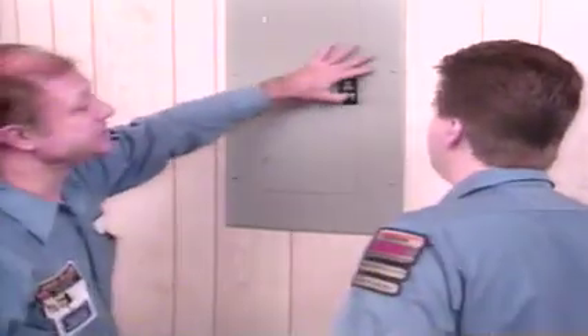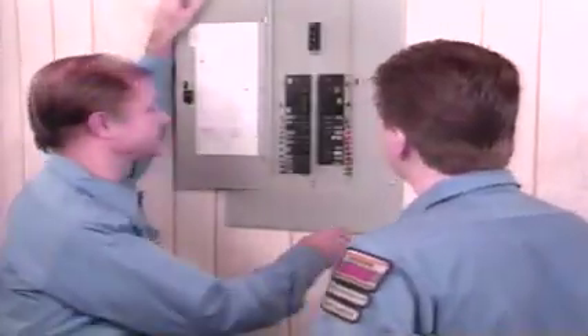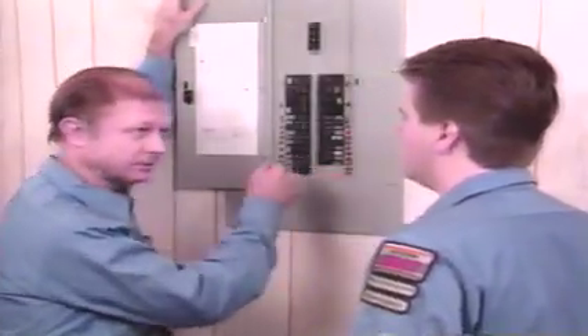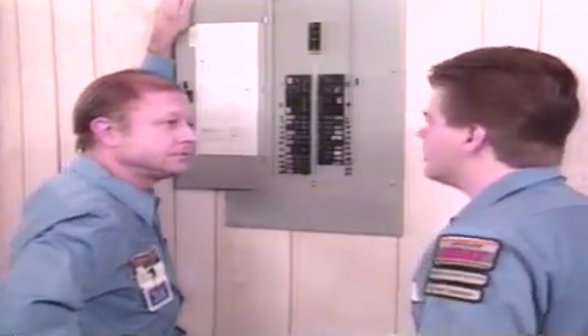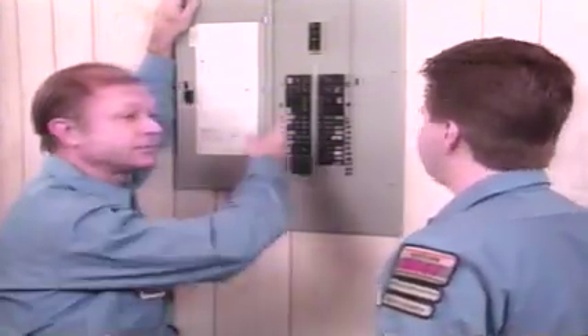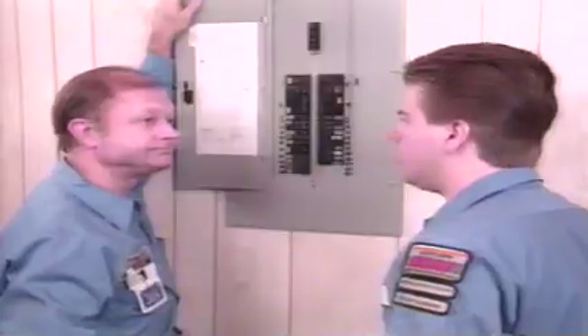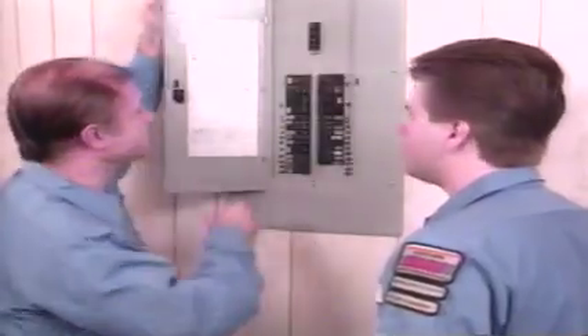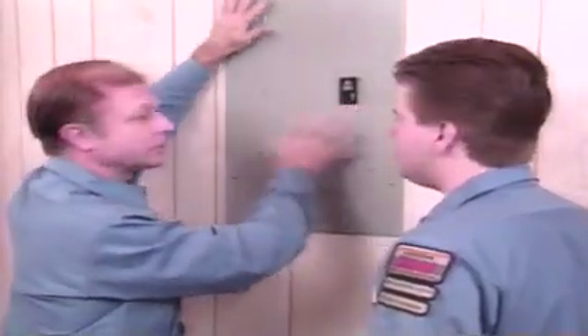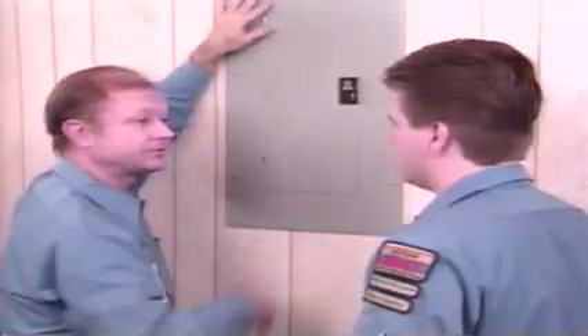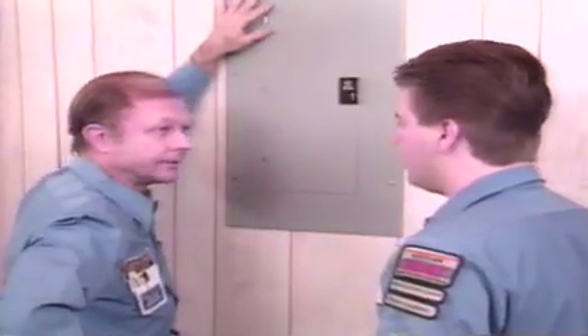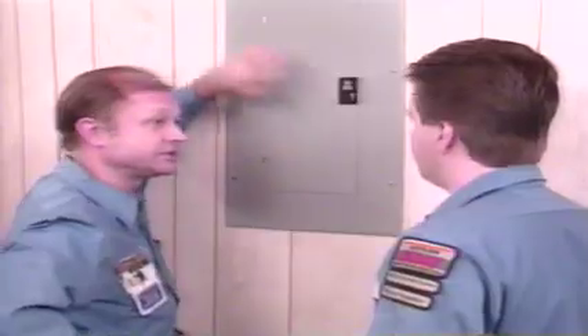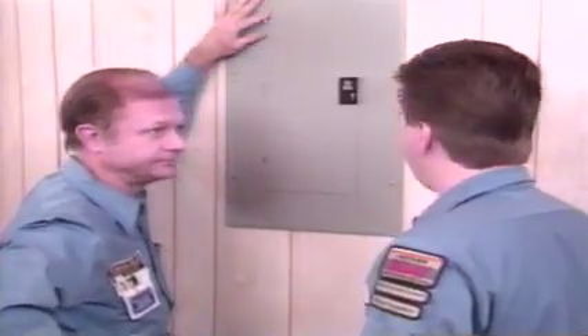Okay, first thing you want to do is disconnect the power to the circuit you're working on. Either flip the breaker or take out the fuse. What if I don't know what circuit's involved? Then take out the main fuse, flip the main breaker. So none of the circuits would be live then? Exactly. Now, once you've done that, it's a good idea to put a note on the door. Let people know that you're doing some electrical work, in case somebody comes to the panel. Right, wants to turn the power back on. Hopefully they'll see the note and they won't turn the power back on. That makes a lot of sense.